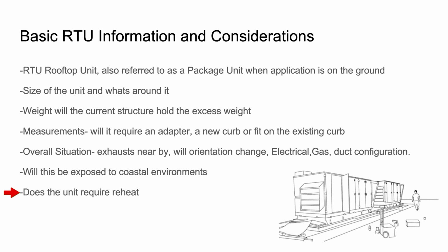And then, of course, a little note about: does the unit require reheat? That's obviously, I've only seen that in commercial applications, but in some cases it does have a big effect on the job. No, I mean, and that's something to look into when you are replacing a unit that's there. You can't just show up and be like, if it was a 5-ton unit, I'm putting in a 5-ton unit, or 20-ton unit, or 50-ton unit. You have to look at what was that old unit accomplishing. So what is it doing for humidity removal? What is it doing for fresh air?